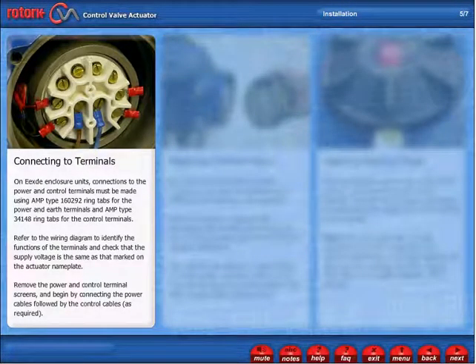Connecting to Terminals. On Eexde enclosure units, connections to the power and control terminals must be made using AMP type 160292 ring tabs for the power and earth terminals, and AMP type 34148 ring tabs for the control terminals.